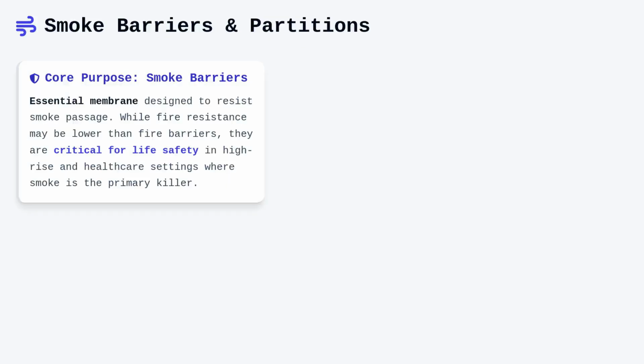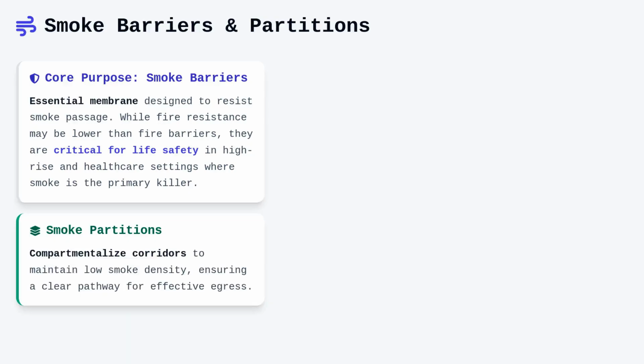Smoke barriers represent a subtle but essential variation, as their primary intent is to provide a membrane capable of resisting the passage of smoke, even if their fire resistance rating is lower than that of a fire barrier. In many healthcare or high-rise occupancies, smoke is actually the primary killer, making these barriers indispensable for creating defensible spaces where occupants can be relocated.